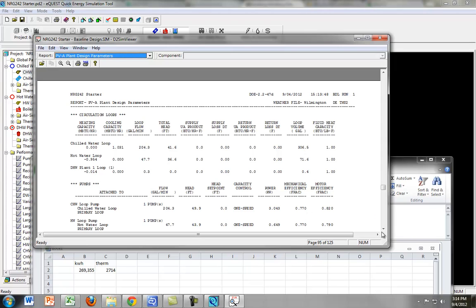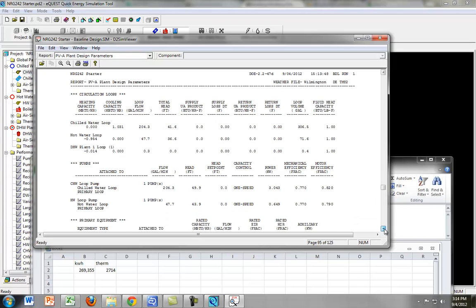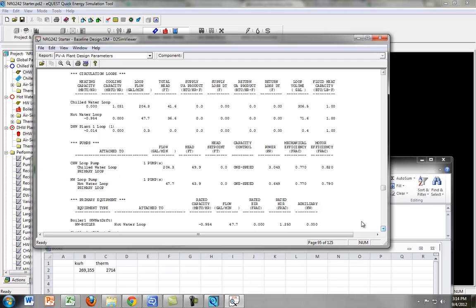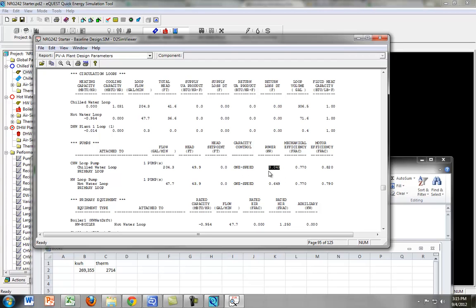Why do we want to look at that? Well, we want to look at that because we want to find the power of the pump. And if we're going to replace this pump, we better replace it with a pump that can put out the same power. So if we're going to replace the chilled water loop pump, the power is about 3 kilowatts, and we have to convert that to horsepower to figure out what kind of pump we want to replace it with.